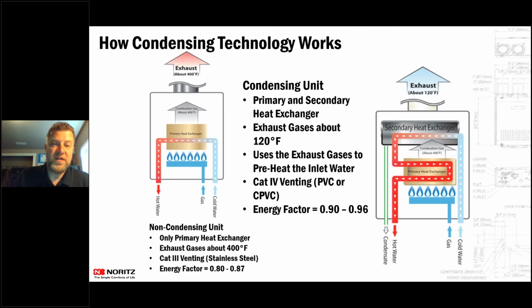The difference between condensing and non-condensing is quite a big difference. Over here on the left, with a traditional non-condensing tankless water heater, you would have that primary heat exchanger and that gas burner. Your flue gases would be about 400 degrees leaving that unit, and with these old non-condensing units, you would see Cat 3 stainless steel venting going off that unit and running all the way outside. Your energy factor would be like 0.80 or 0.87, which is still more efficient than a tank water heater.